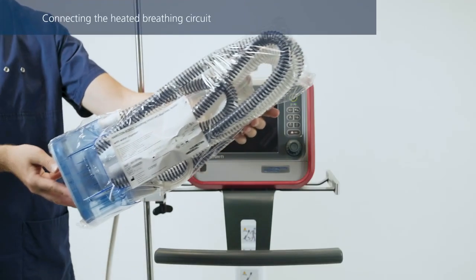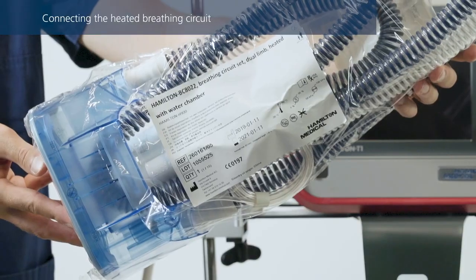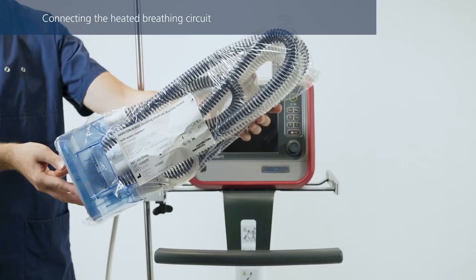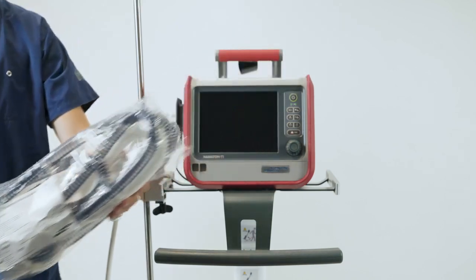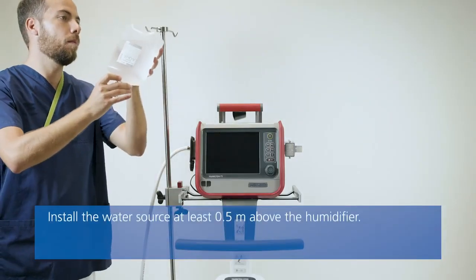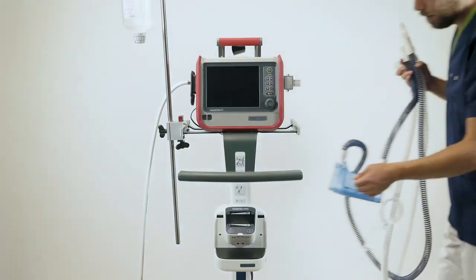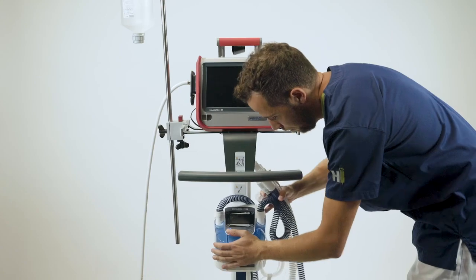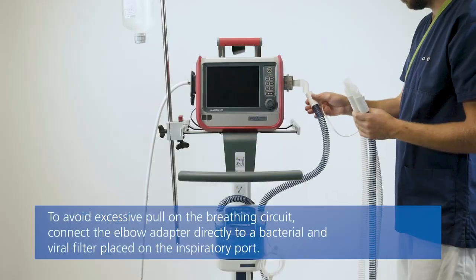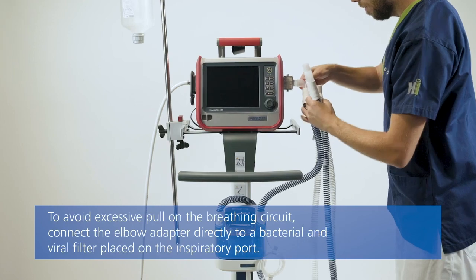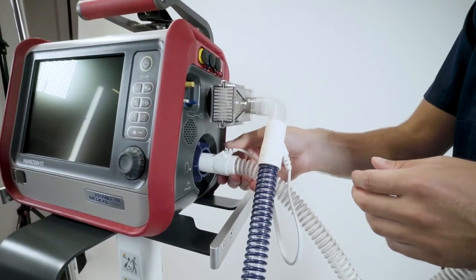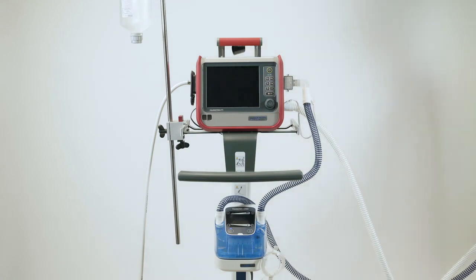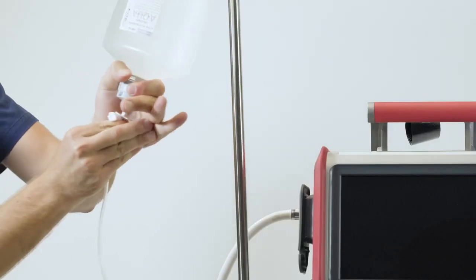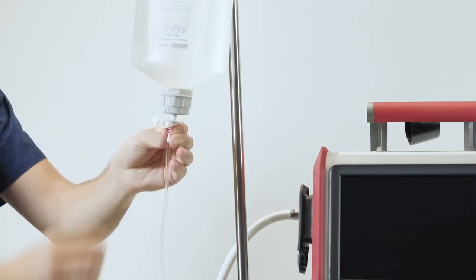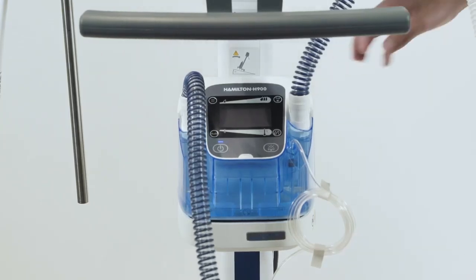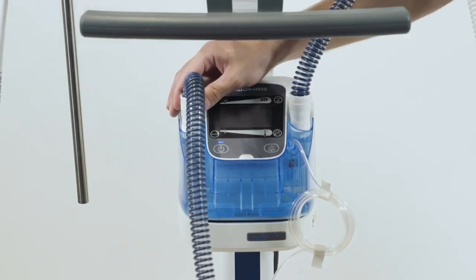The following information applies if you are using the Hamilton BC8022 breathing circuit or any other double-limb breathing circuit for an active humidifier. Install a water bag or bottle above the humidifier. Firstly, insert the humidifier chamber. Connect an elbow adapter. Connect the shorter blue tube to the inspiratory port on the ventilator, and connect the expiratory tube to the expiratory valve. Then insert the water feed line into the water bag or bottle. Make sure that all the electrical contacts on the breathing circuit match the connecting element on the humidifier.